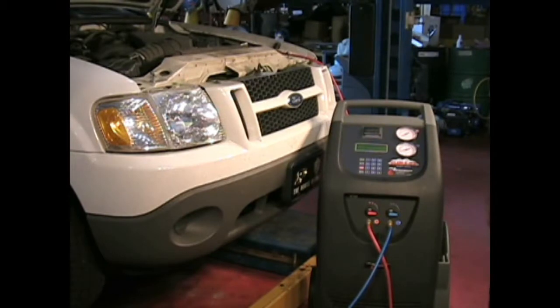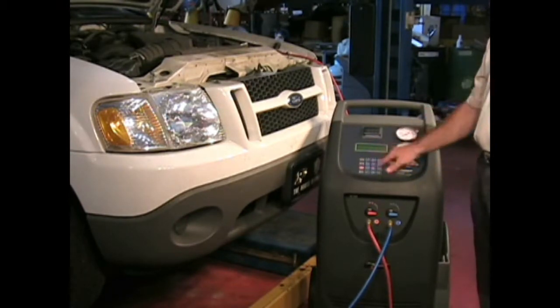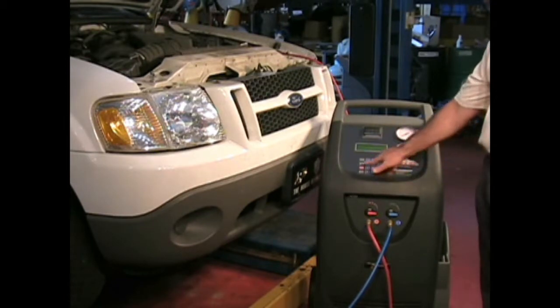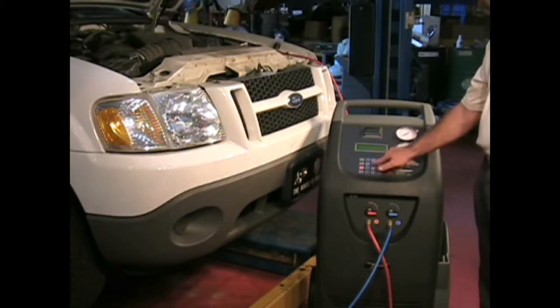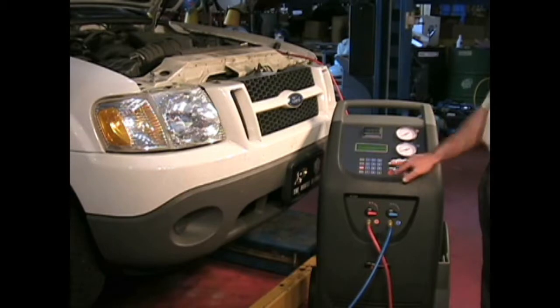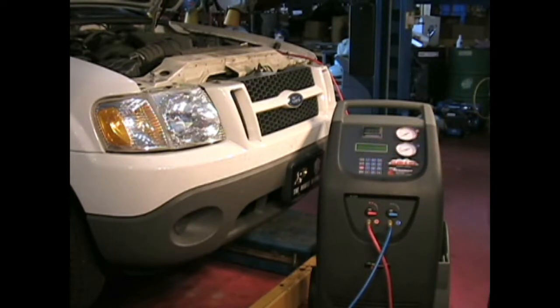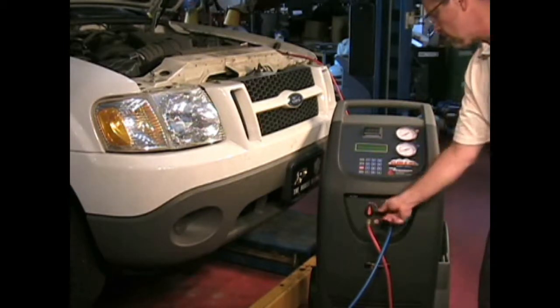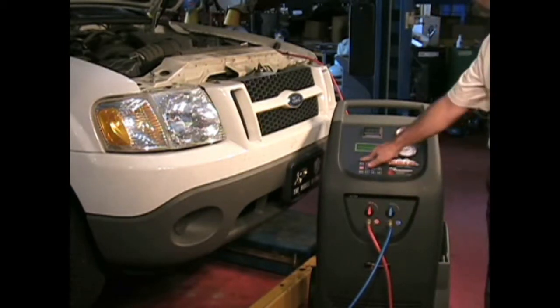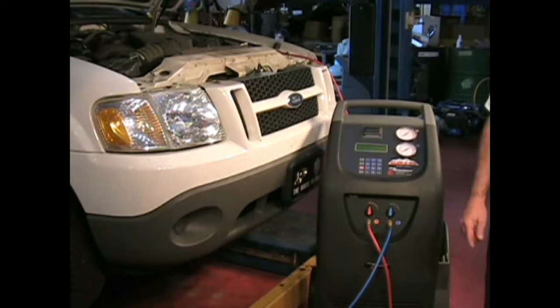To vacuum or evacuate a system, arrow to Assisted Procedure and press Enter. Then arrow to Vacuum. Enter your desired vacuum time and press Enter. Should you desire the unit to perform a leak test, set the vacuum time for at least 15 minutes. The display will prompt you to open the high and low side taps and press Start. The vacuum pump will run for your preset time.